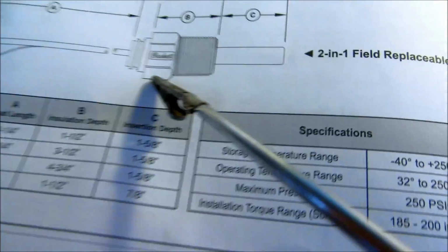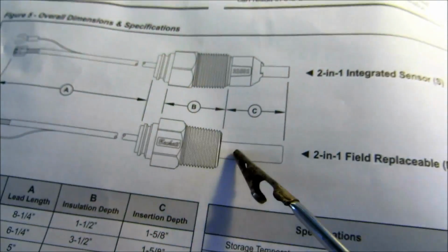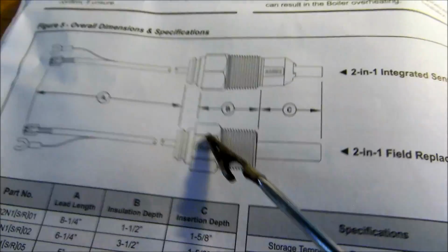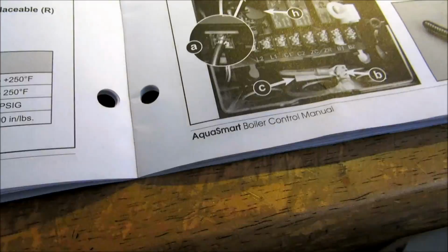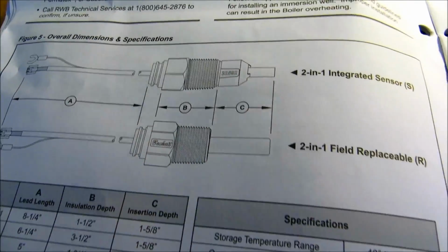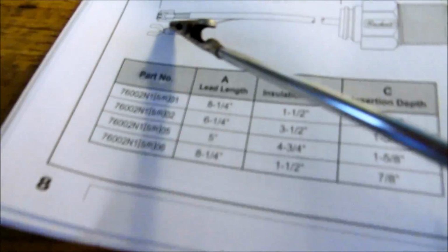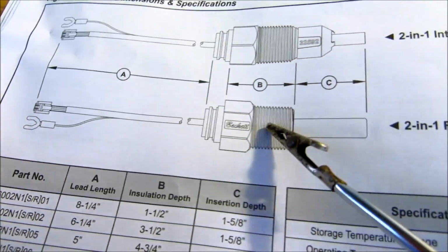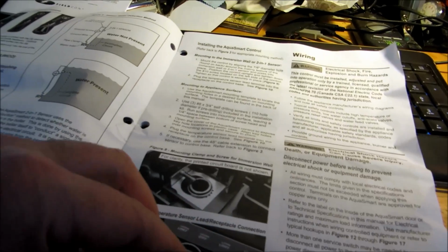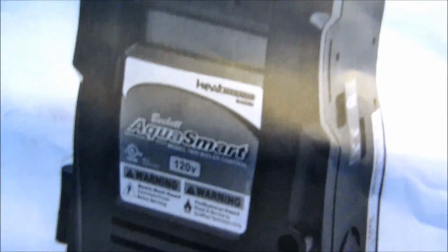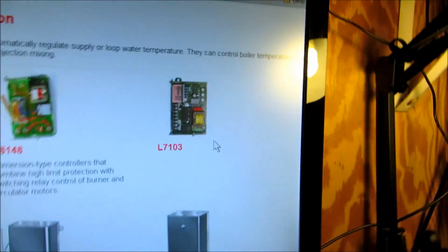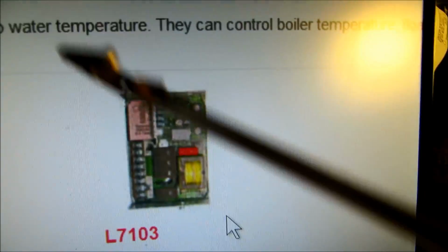And if you look at this, this well is all plastic. Years ago they were all brass, but not this junk. It's all plastic. I've had problems with these. What happens is it says it's on low water, and that probe's not in all the way. It's a plastic probe right there. That thing has to be pushed in all the way. Piece of junk. Aqua Smart, my foot.